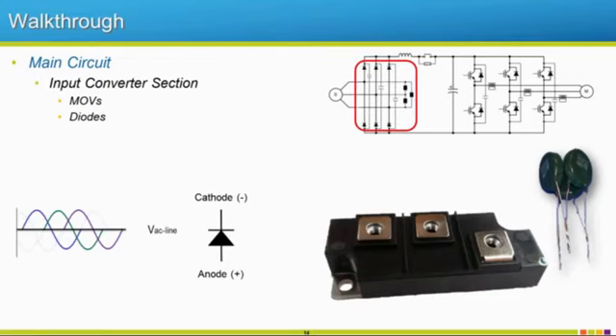So for our input side, you notice up in the top corner we just have our picture. We're talking about just the input, so the converter side. This is made up of some small capacitors and these units right here, these are MOVs. So these are going to try to get rid of any excessive voltage transients that could come in, let's say like a lightning strike or something like that. It's going to try to protect this more expensive part right here, so these input diodes that we have coming in here.